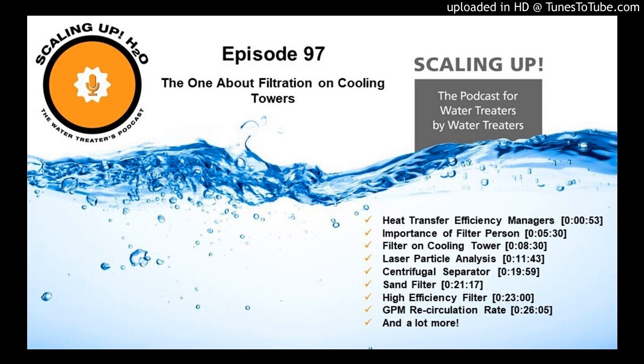The end result is that the particulate that comes into the cooling tower is at about a 1/2 micron. Most of the stuff floating around in the air is 2 microns down to a 1/2 micron and some finer, so it's really fine. When that particulate goes into the cooling water, it flows out through the whole system. As you get more and more particles in the water, they agglomerate, and the water becomes more turbid. Then the sump begins to do its job, and particulate settles out there, but it's also settling on the heat transfer surfaces.